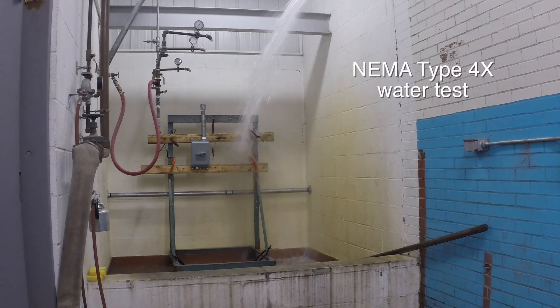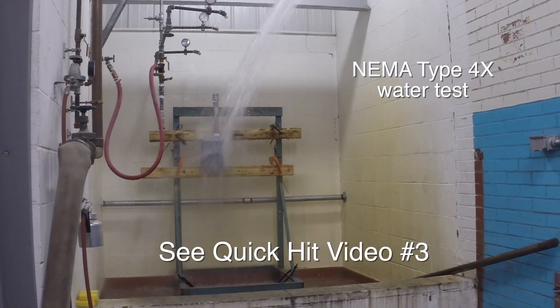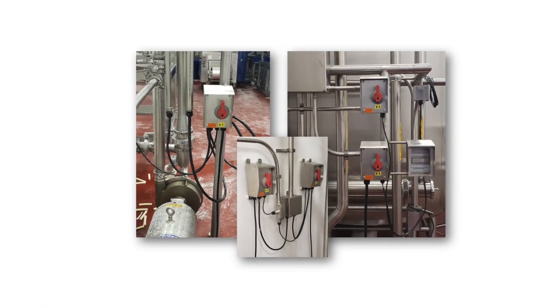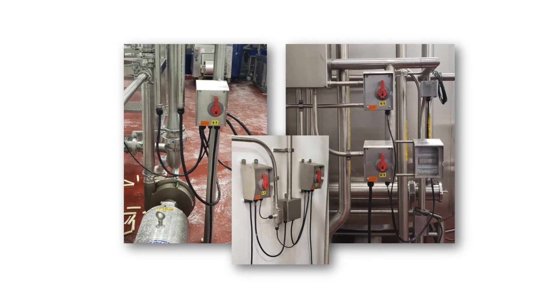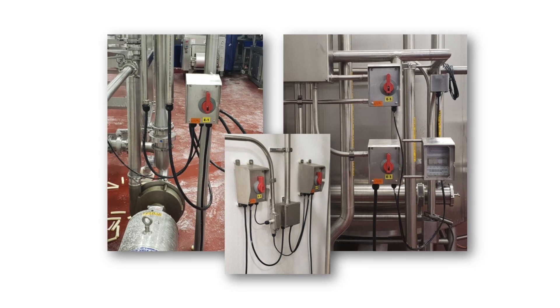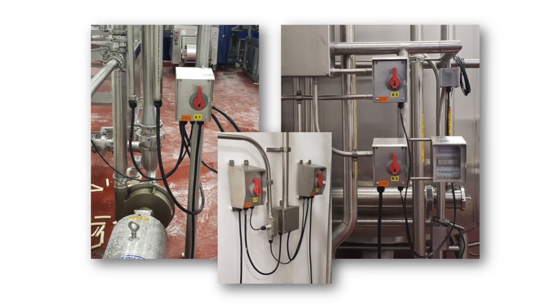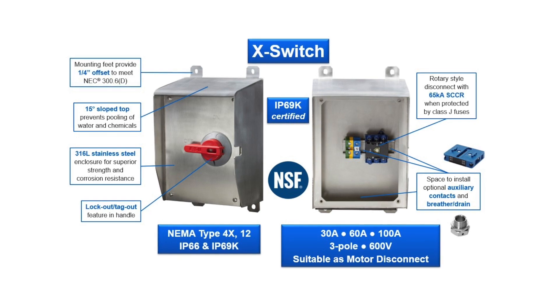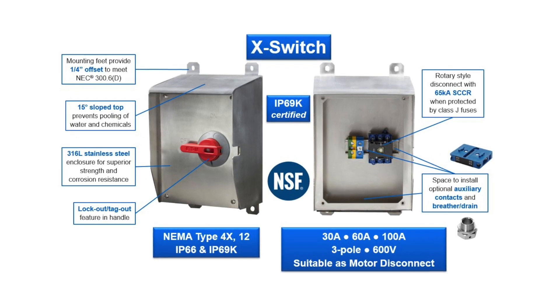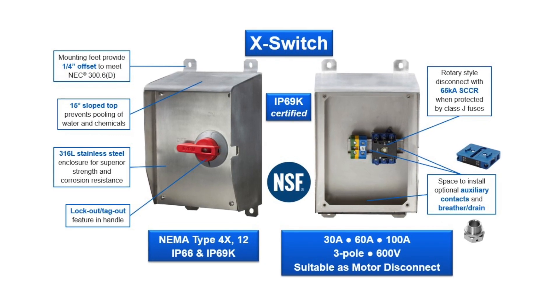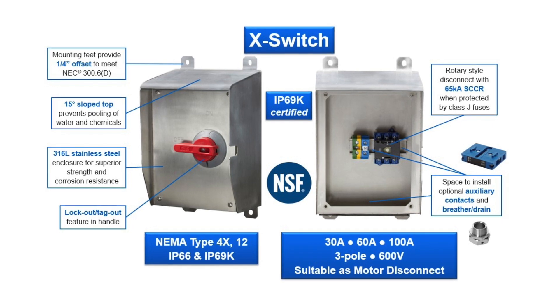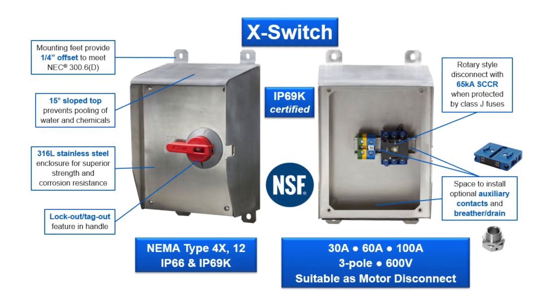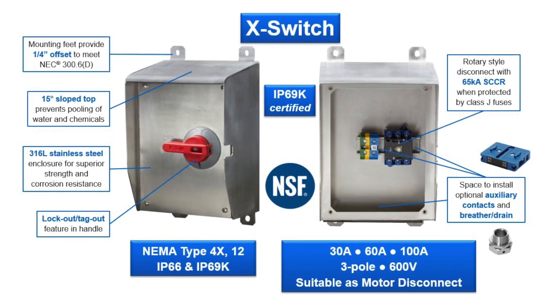These units also carry an NSF rating for use in food processing areas. Many of the referenced environmental ratings were fully explained in a previous video. Here's an example showing one of these disconnects being subjected to the NEMA 4X water test. Aeroheart was the first to introduce a motor control disconnect in a stainless steel enclosure with a small footprint, specifically designed for food processing areas with high-temperature washdown. The second-generation X Switch is shown here along with its key features and ratings — note the mounting feet with a quarter-inch offset, the sloped top, the 316L stainless steel enclosure, and the IP69K rating. An optional breather drain can be installed in the bottom of the enclosure to prevent water buildup due to condensation, which is typically present in a food processing environment.